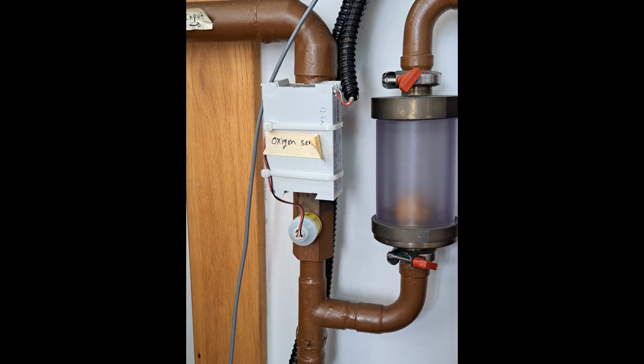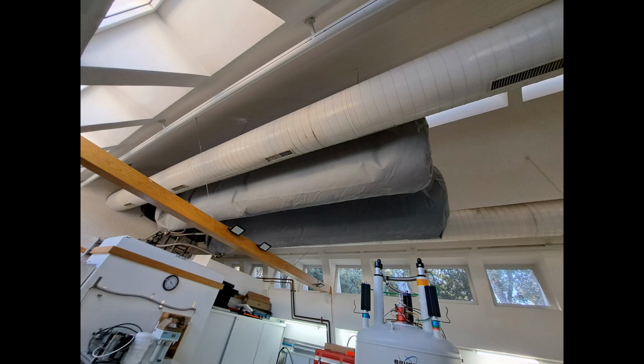The helium arriving from the installation is monitored for oxygen impurities that indicate contamination with air. If the level of oxygen is greater than 0.4%, indicating 2% air, the input valve to the gas meter is closed and a valve open to dump the gas into the air. There is a transparent tube containing a ball that gives a visual indication of flow and a manual valve to bypass the meter in case it needs to be removed.